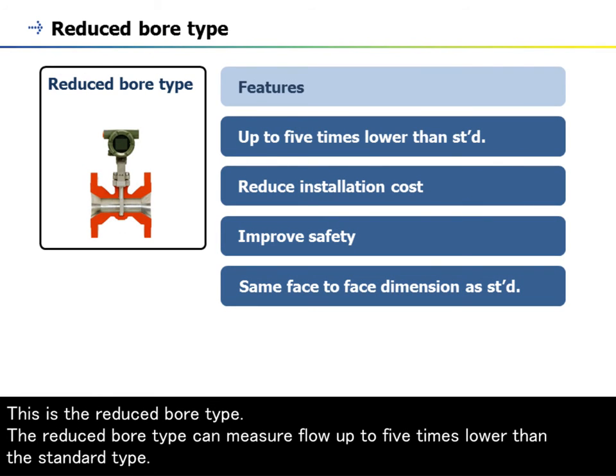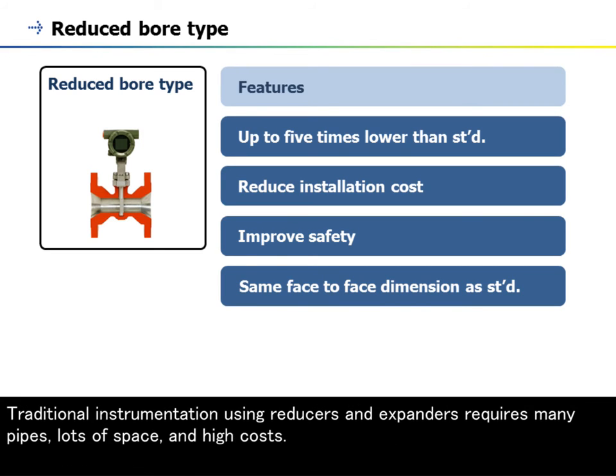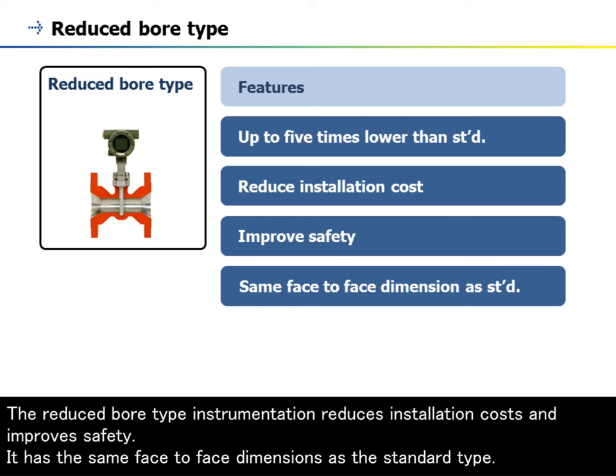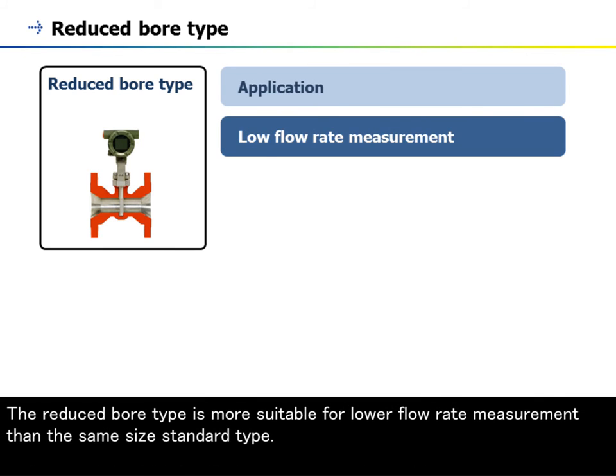This is the Reduced Bore Type. It can measure flow up to five times lower than the standard type. Traditional instrumentation using reducers and expanders requires many pipes, lots of space, and high costs. The reduced bore type reduces installation costs and improves safety. It has the same face-to-face dimensions as the standard type and is more suitable for lower flow rate measurement.